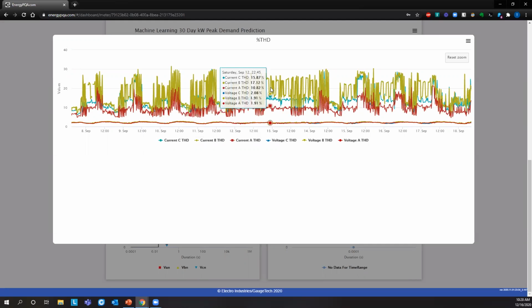So what we have to do is narrow down, again, with our equipment level monitoring with the ST40. We can put the ST40 on multiple pieces of equipment to see exactly where these high harmonics are coming from. We can isolate that piece of equipment from everything else with a filter or some sort of protection, so this equipment does not feed back and affect the operation of all of our other devices in this building.